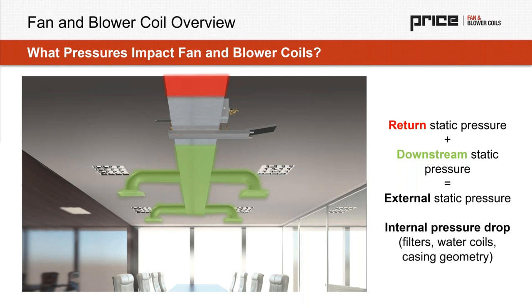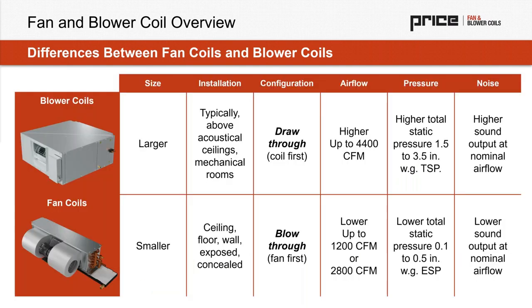So there's actually many applicable answers here. The reality is blower coils are traditionally larger. They supply higher CFMs and they can work through higher total static pressures. A fan coil is much smaller, lower CFM, and generally is installed with shorter duct runs or maybe almost no duct run at all, with integrated supply air outlets or return air outlets directly into the product.